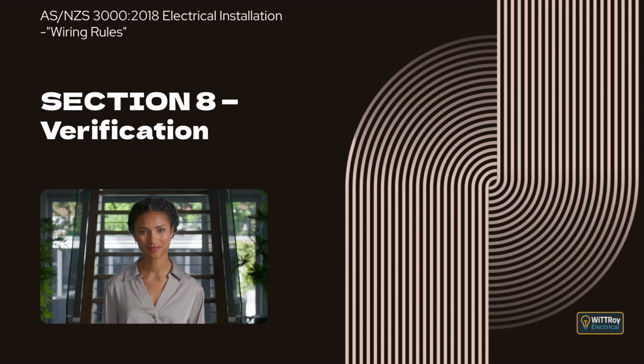The inspection confirms that special installation conditions are met, including locations affected by water, explosive atmospheres, extra low voltage, or high voltage. Compliance with the required standard is confirmed, along with correct connection, support, and fixing. Protection against external influences, including ingress of moisture where required, is checked, and the suitability of equipment for the intended voltage, current, and frequency is confirmed.